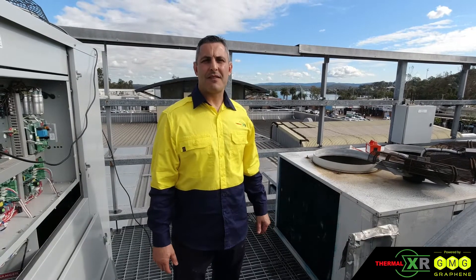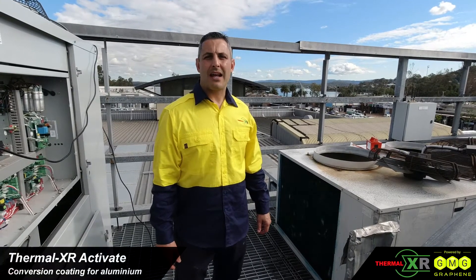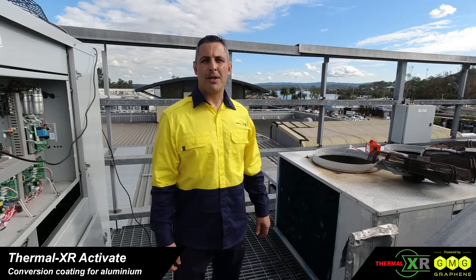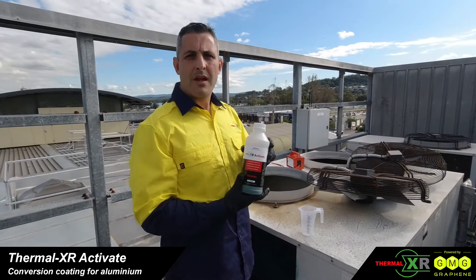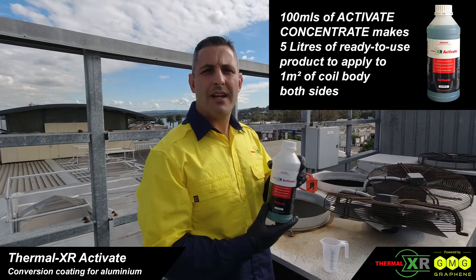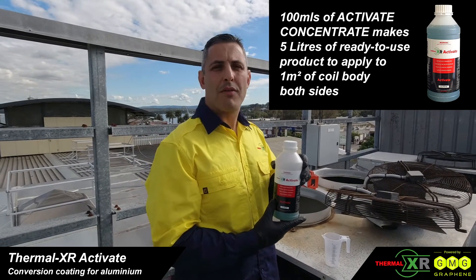Now we're at the second phase of the process — applying Thermal XR Activate. Thermal XR Activate is a nano coating that's left on the surface of the aluminium to maximise adhesion of the Restore. We need 100ml of concentrate to give us 5 litres of ready-to-use product for one square metre of coil body.